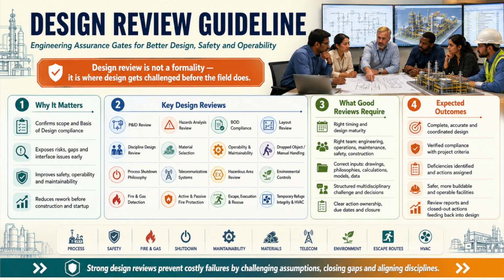The process shutdown philosophy review defines how the plant fails safely. Starting from the highest shutdown level, you establish the hierarchy, boundaries, initiation logic, isolation requirements, interactions, escalation paths, reset philosophy, and relationships between existing and new facilities. You must examine normal operation, startup, shutdown, maintenance, partial operation, equipment failure, utility loss, fire, gas release, and emergency response. Any unresolved boundary must be recorded as a hold point with a named owner. Ambiguous shutdown logic is not flexibility. It is latent operational risk.